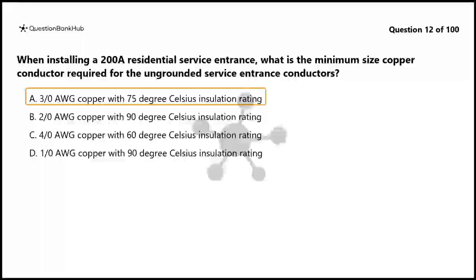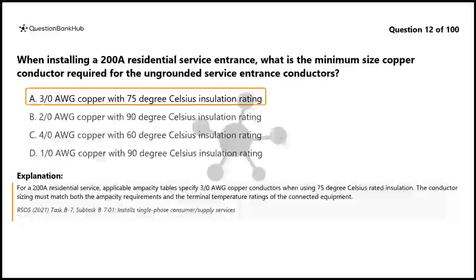The correct answer is A. 3/0 AWG copper with 75°C insulation rating. For a 200 amps residential service, applicable ampacity tables specify 3/0 AWG copper conductors when using 75°C rated insulation. The conductor sizing must match both the ampacity requirements and the terminal temperature ratings of the connected equipment.